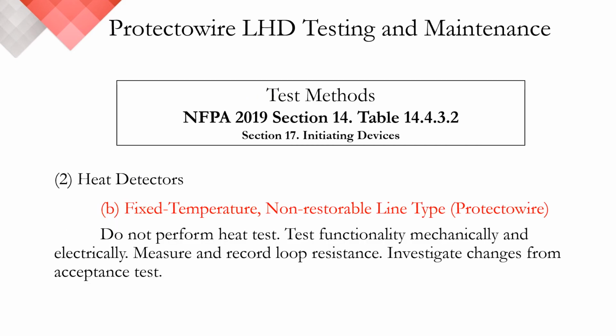Today, we exclusively focused on refrigerated and freezer warehousing, but this slide universally applies to Protectowire. Complying with NFPA 72 testing and maintenance is remarkably simple. Given our products are defined as a fixed temperature, non-restorable line type detector, there is no requirement to perform a heat test per NFPA 72. Despite this, if anyone would like to see a functional test performed, we advise installing an additional service loop near the end-of-line device. This will allow the service loop to age in the same environmental conditions as the balance of the zone. You can then heat test a small portion of the service loop and then reconnect or splice the detector and complete the balance of your inspection and testing.